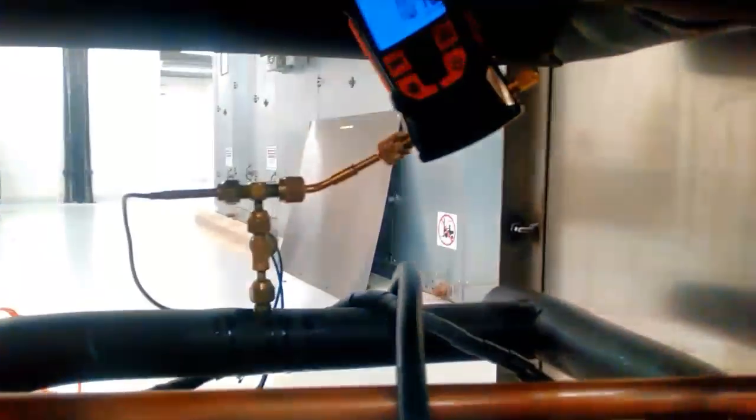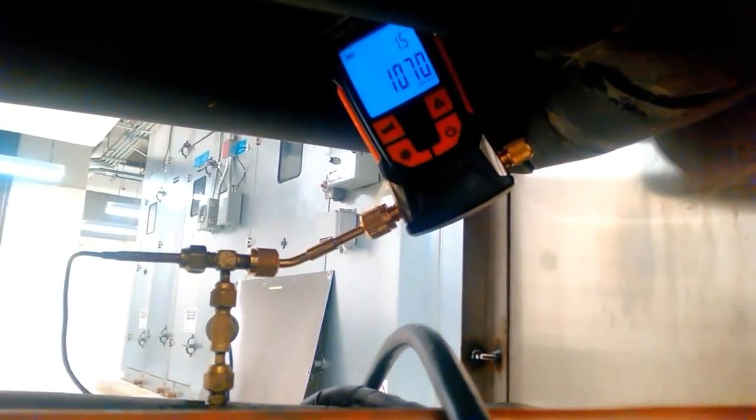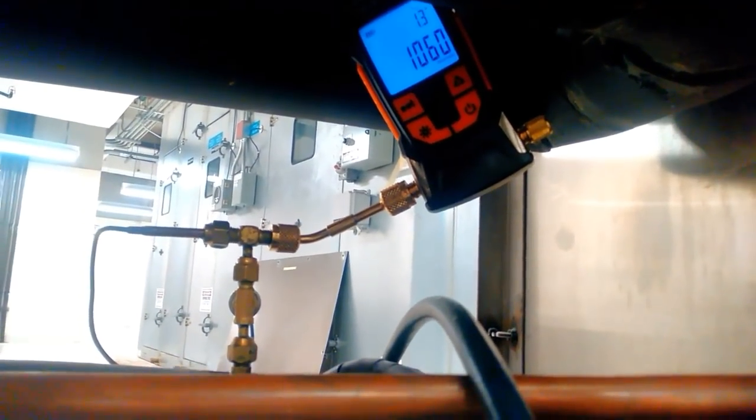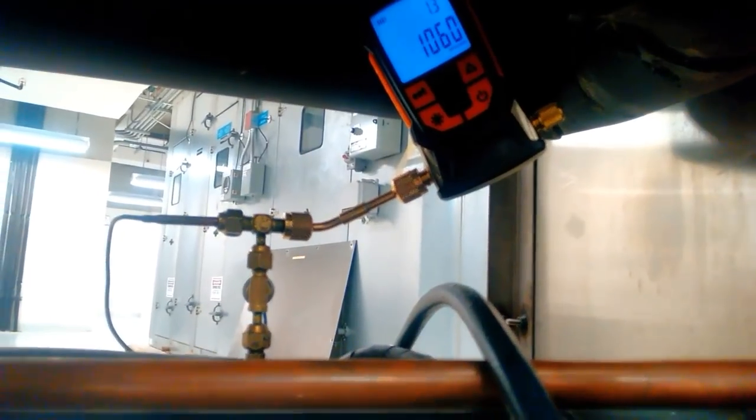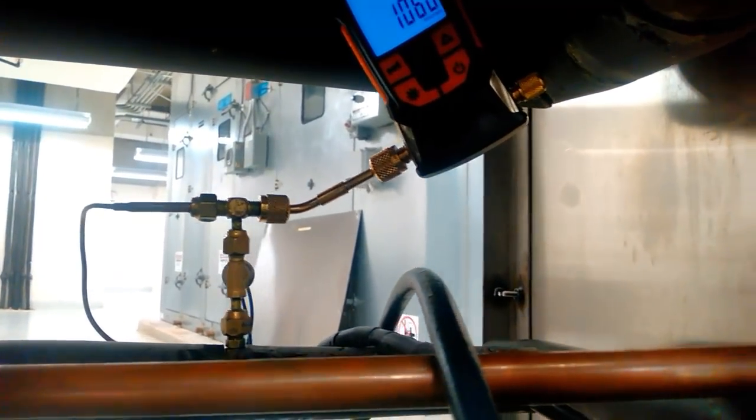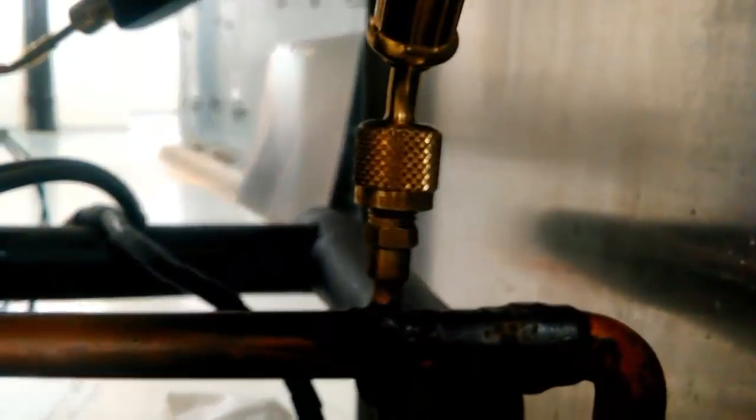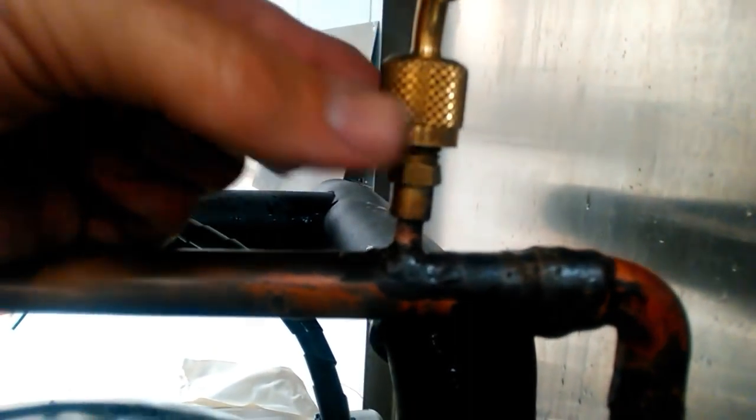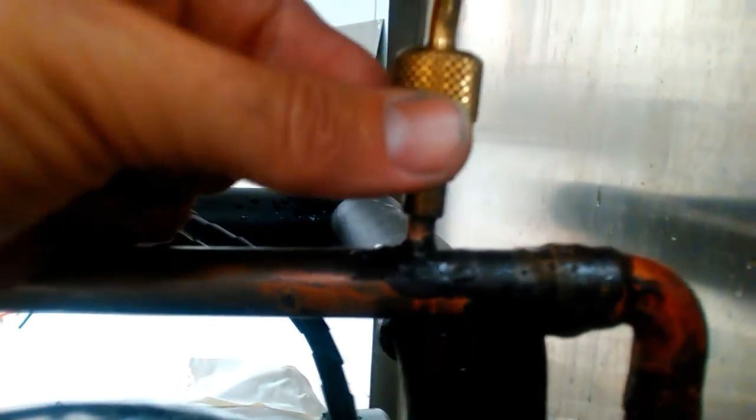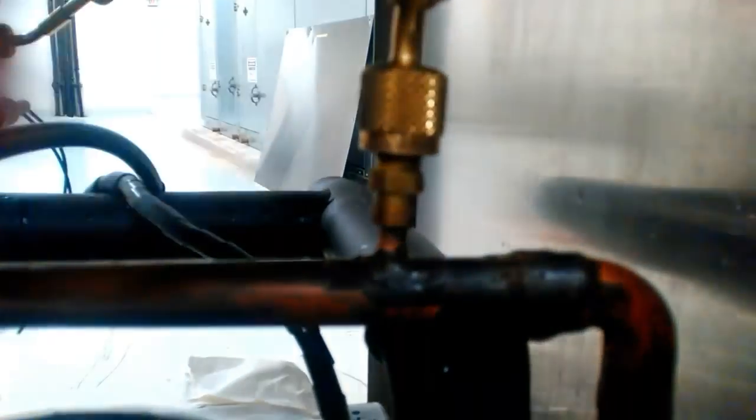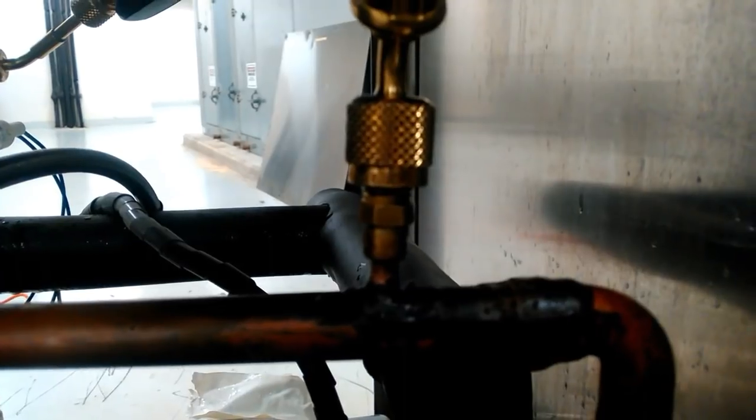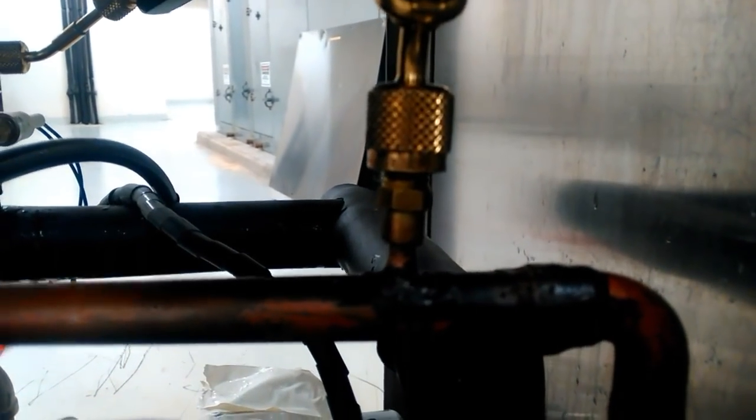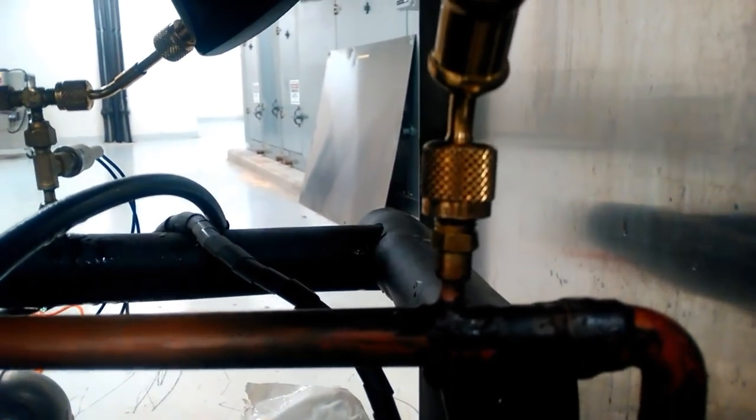And the other thing, if you notice, my micron gauge is on the system. Luckily, I had another service port that I could put it onto the system from. You want your micron gauge on the system. You don't want it attached to your vacuum pump. Now, if we had a valve here, your core removal tool, which is also a valve, has a T on it and you can put your micron gauge on there as well. That way, it's on the system side, not on the pump side. Very important.